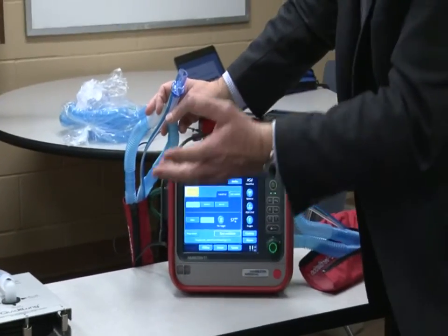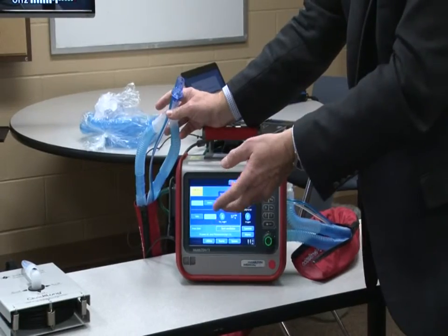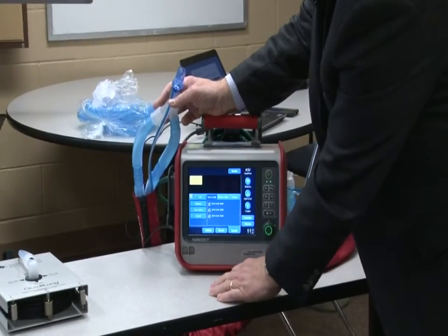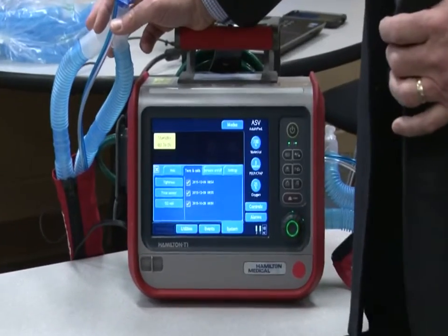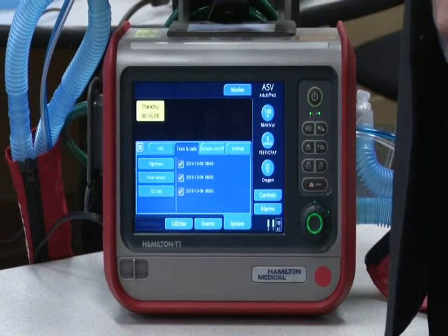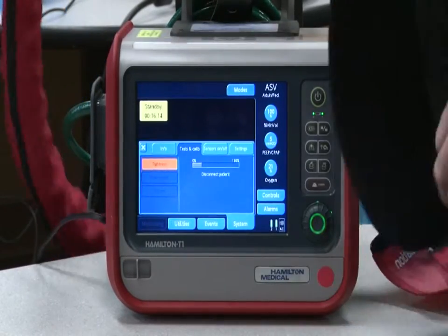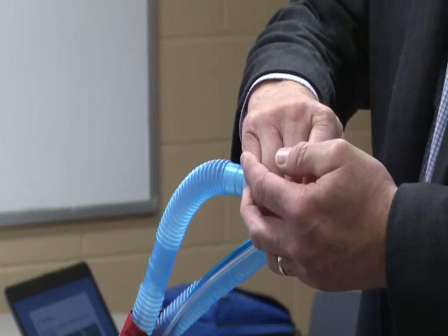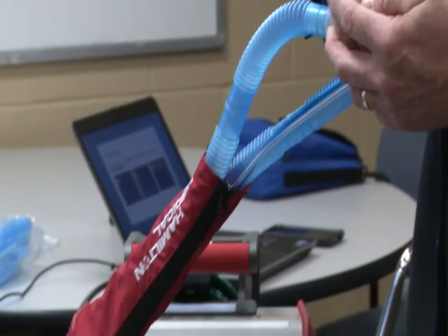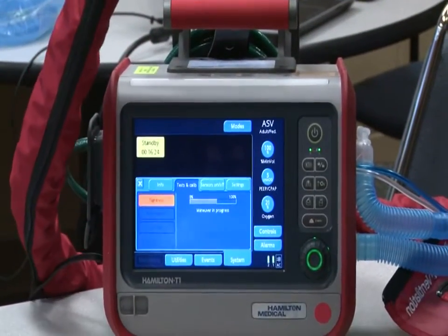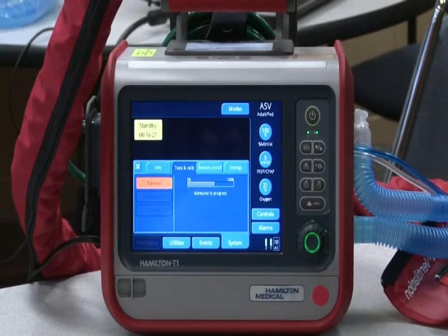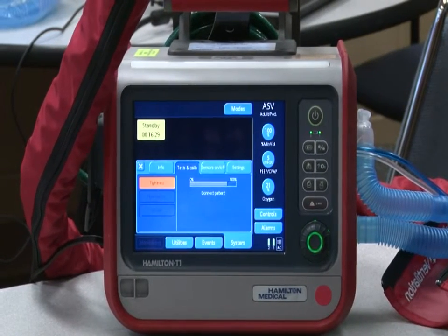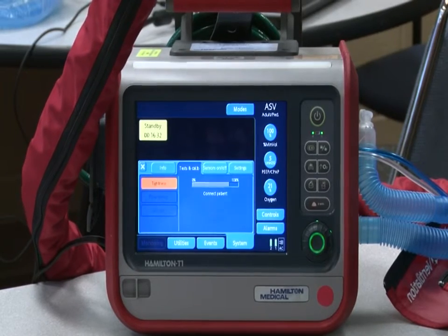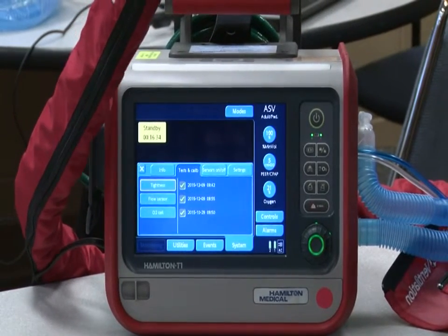Okay. If the screen probably disappeared, you just touch the pre-op check button again. What is the time limit on that? On what? 30 seconds. Yeah, I think it's 30 seconds. So I'm going to touch the tightness test. Now I'm going to occlude it, and it'll tell you down there underneath the little time bar. And so keep it occluded. And you'll hear the vent cycle the expiratory valve. And then you'll get a check.